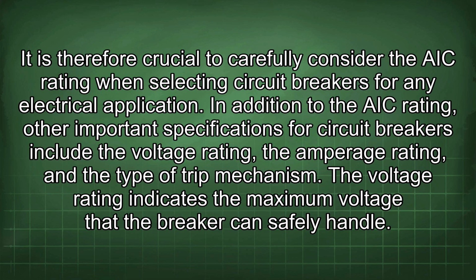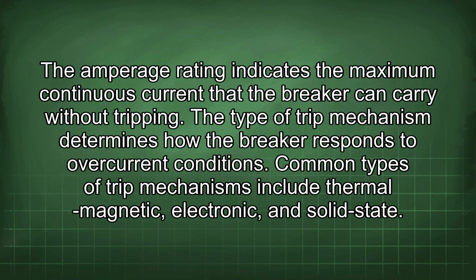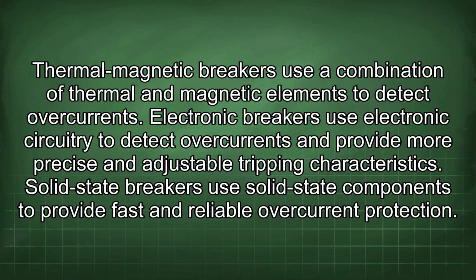The voltage rating indicates the maximum voltage that the breaker can safely handle. The amperage rating indicates the maximum continuous current that the breaker can carry without tripping. The type of trip mechanism determines how the breaker responds to overcurrent conditions. Common types of trip mechanisms include thermal magnetic, electronic, and solid state. Thermal magnetic breakers use a combination of thermal and magnetic elements to detect overcurrents. Electronic breakers use electronic circuitry to detect overcurrents and provide more precise and adjustable tripping characteristics. Solid-state breakers use solid-state components to provide fast and reliable overcurrent protection.